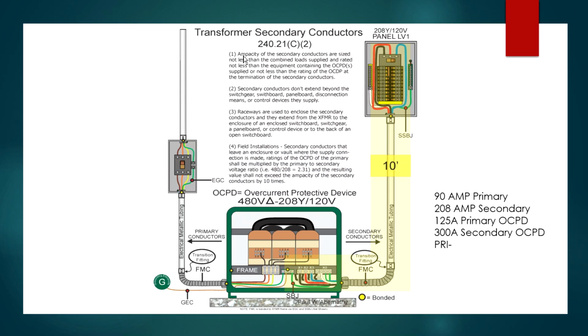Okay, number one, it says the ampacity of the secondary conductors, these right here, must be not less than the combined load supplied. So whatever his load calculation is, let's say his load was 180 amps. You think, well, wait a minute, isn't that more? But then it goes on to say, and rated not less than the equipment containing the overcurrent protection device, or whatever the equipment might be, supplied, or not less than the rating of the overcurrent protective device at the termination of the secondary conductors. So in our case, if this was a 200 amp device protecting this panelboard as well under 408.36, then this is 200. That's the limiting of the load. This conductor here is good for 200 amps because it's a 3/0 copper. So everything's good. So we met this first rule.